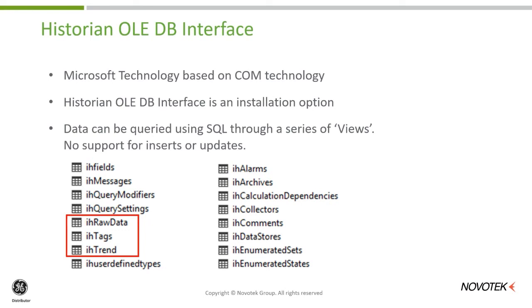There are a wide number of tables available, but for most people we're interested in three key tables. First, IH Raw Data, where all raw data from tags is stored. Then IH Tags, which stores all tag information including name, description, data source, and update frequency. And finally IH Trend, which is useful when you want to pull back multiple columns of data at the same time.